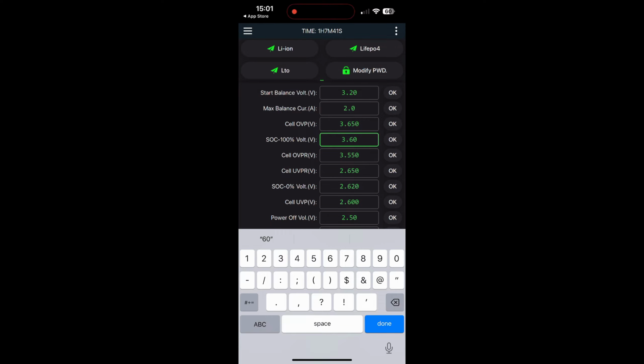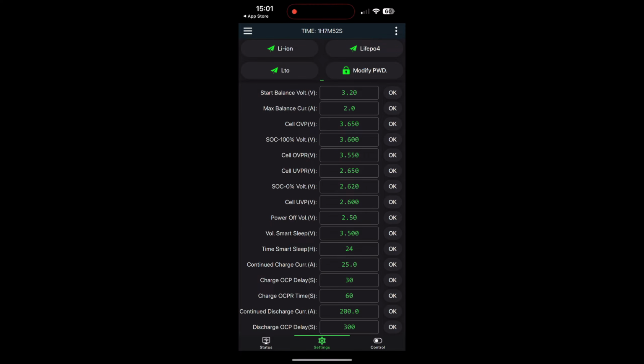So again, before we used to set the over voltage protect to 3.6 and then the over voltage protect reset to 3.55. But now that we've got this new setting, what will happen is when you're charging the cell, the individual cells will be measured, and as soon as one cell gets to 3.6 volts, it's going to treat the pack as if it's 100% charged. Okay. Now, if it ever reaches 3.65, it's basically going to disconnect all the charging mechanisms, which it should be doing when it's at 100% SOC anyway.